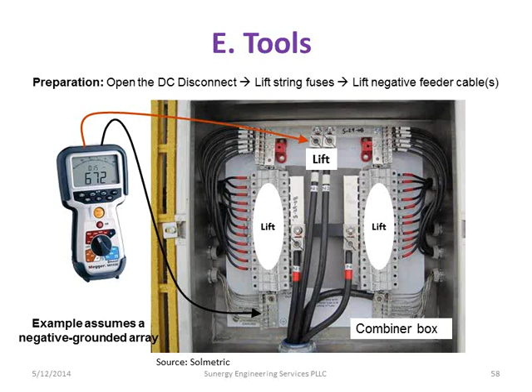So now we get into the fun tools. The combination tools, these are the ones that were made in Europe to do all of the IEC required tests. And they're really nice because basically the ground continuity is a separate test, but the polarity, the open circuit voltage, the short circuit current, and the insulation resistance is all done automatically by the press of a button. So you make all your wiring connections with a tool, you hit a button, and it does all the tests for you all at once. And it saves it to a file, and then you can download that file as part of your documentation of your commissioning.